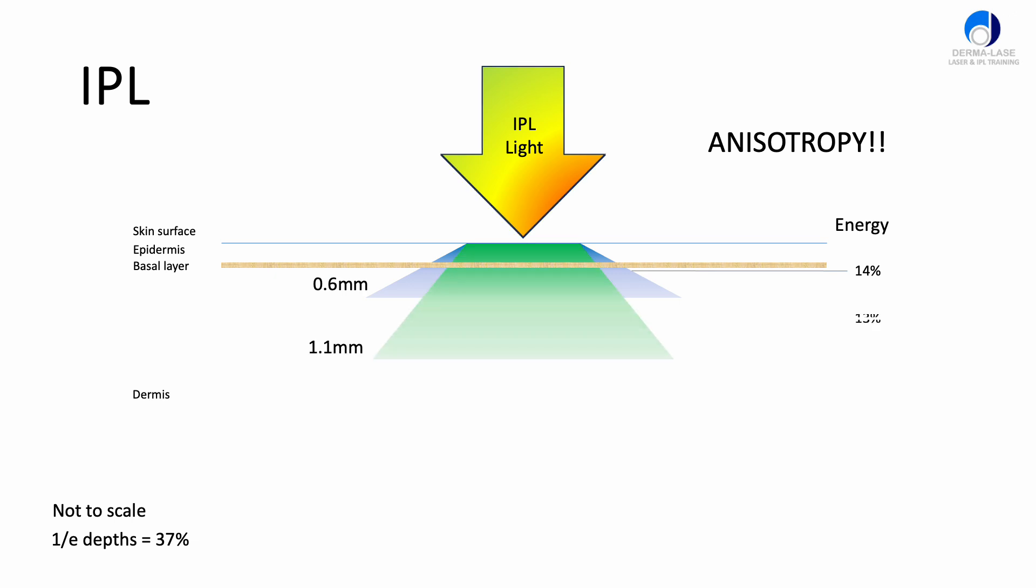Then we have the green light which is almost the same as blue, about 13% of the total energy, but it penetrates a little bit deeper about 1.1 millimeters because its anisotropy is not as wide as with blue light. Then we have the yellow light. There's only about 4% of the energy in the yellow part of the spectrum so it's a relatively small region of the overall output but it does penetrate a little bit deeper, about 1.6 millimeters in depth.